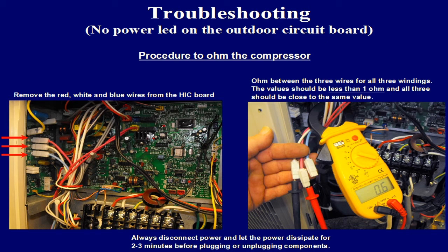The winding resistance is generally 0.4 to 1 ohm between any 2 windings. This resistance may vary some depending on the outdoor ambient temperature. If no resistance is shown, check the compressor terminal connections at the compressor as well.